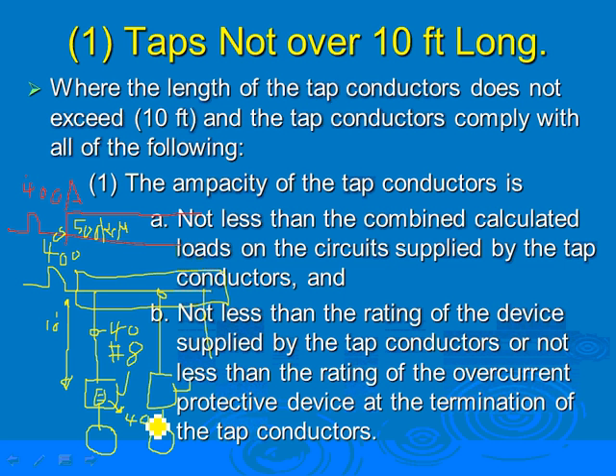Any comments, guys? Any questions about that? So that's so you can do your math now. If you have a 1,000 amp feeder unit tap here, multiply by 1/10 of that, it'll get you 100 amp. The minimum is 100 amp. The other condition is you can't move this disconnect further than 10 feet away from this gutter. Otherwise, that's not a 10-foot rule.